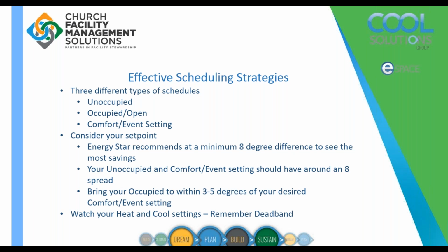Now with churches, throughout the day we've got multiple events happening at different times, different things going on. That's why we recommend having that occupied setting, which is interim, in between the unoccupied and the comfort event setting, because it's easier and quicker to get a room down to set point if it's 4 degrees warmer or cooler than your setback. And that's why we say bring the occupied to within 3 to 5 degrees of your desired event setting.